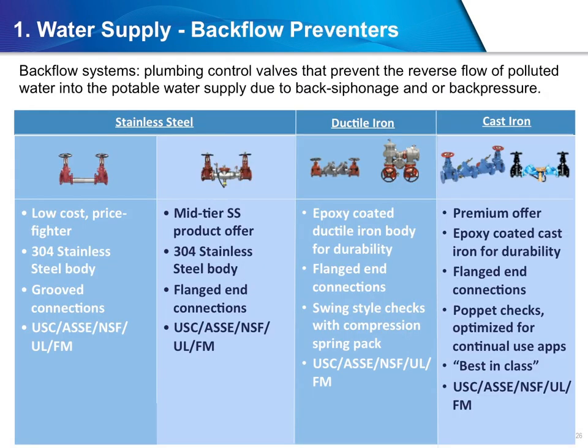Among the common approaches to protecting water quality in a water supply system, the use of backflow preventers is typical. Backflow systems are essentially a series of plumbing control valves that prevent the reverse flow of polluted water from entering into the potable water supply due to back siphonage or back pressure. While backflow preventers may not have a direct relation to Legionella control, they should be part of a control measure in a water management program. When selecting backflow preventers, there are choices to consider. Stainless steel versions are available as basic or mid-tier products with some limited options. More robust and durable choices include ductile iron valves, some with epoxy-coated paint on the exterior and designs for continuous or heavy usage.